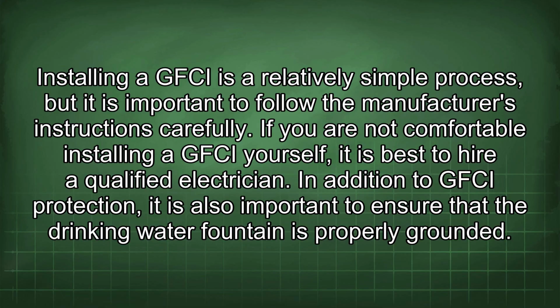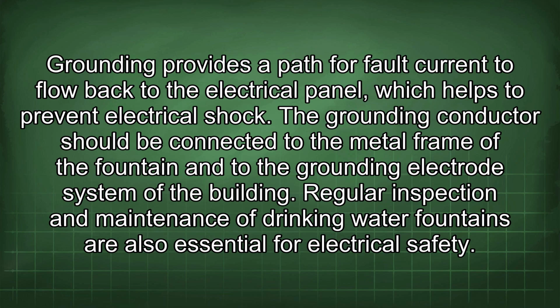In addition to GFCI protection, it is also important to ensure that the drinking water fountain is properly grounded. Grounding provides a path for fault current to flow back to the electrical panel, which helps to prevent electrical shock. The grounding conductor should be connected to the metal frame of the fountain and to the grounding electrode system of the building.